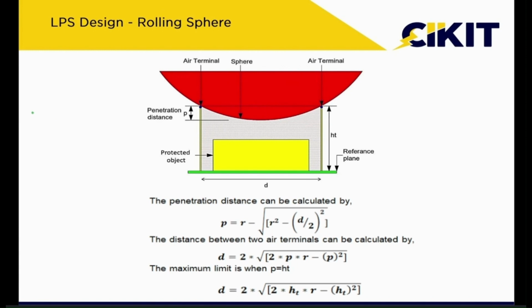And if you observe this formula, you can observe that it depends upon two parameters. One is the penetration distance and the second one is the radius of protection. The radius of protection depends upon the level of protection, whereas the penetration distance is the distance up to which the sphere is coming below the center.